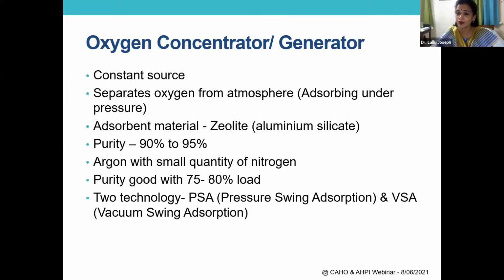Purity is very good when you actually use it between 75 to 80% load. Now, if you have a 25 meter cube per hour plant, you can't load it completely, then your pressures will drop and the purity will also drop. So up to 75 to 80% load is what your concentrator can take. There are two technologies, the PSA and the VSA. PSA is pressure swing adsorption and VSA is the vacuum swing adsorption, which is a patented technology.